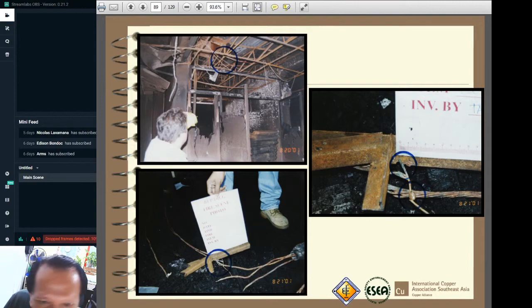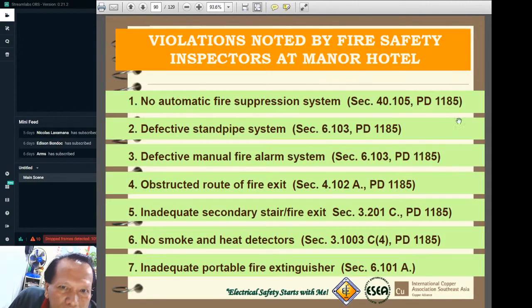Again, additional pictures showing the damages of the feeder that might have been overloaded. These were the findings by the Bureau of Fire on the Manor fire. See, no automatic sprinkler system. It is a hotel, so if it is a hotel, a sprinkler system should be mandatory. The fire water standpipe is also defective, the manual fire alarm system is also defective, and the road to the fire exit is also obstructed.